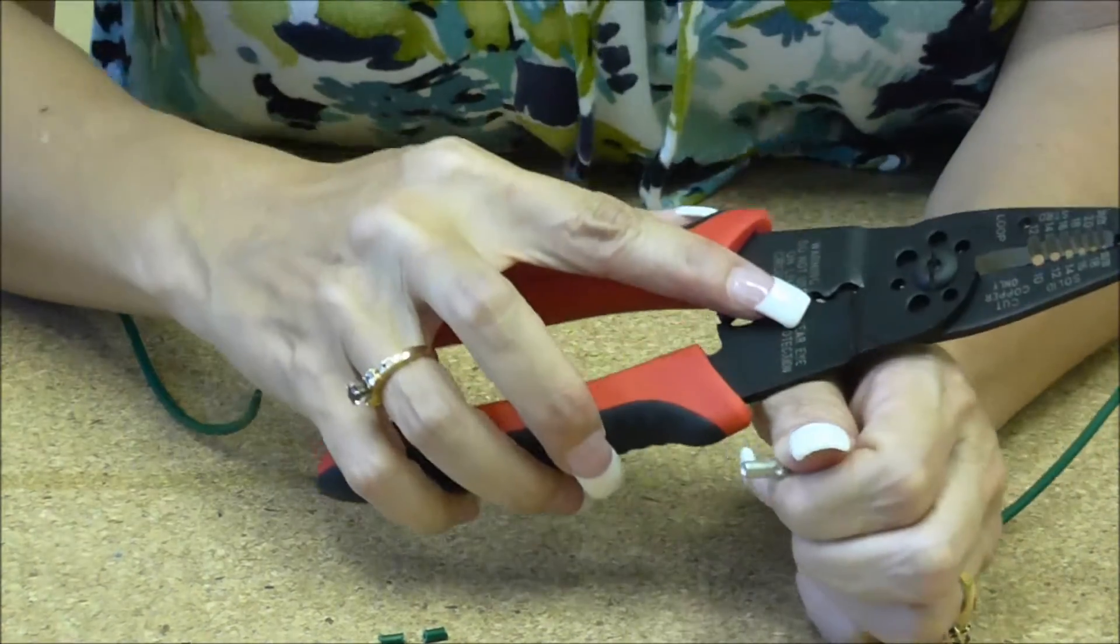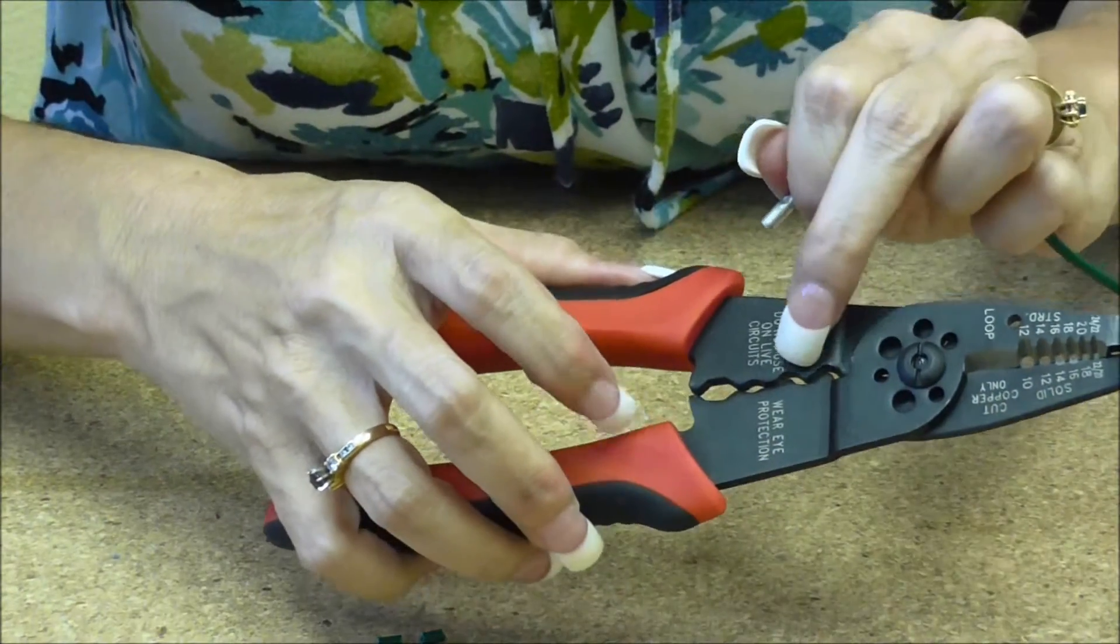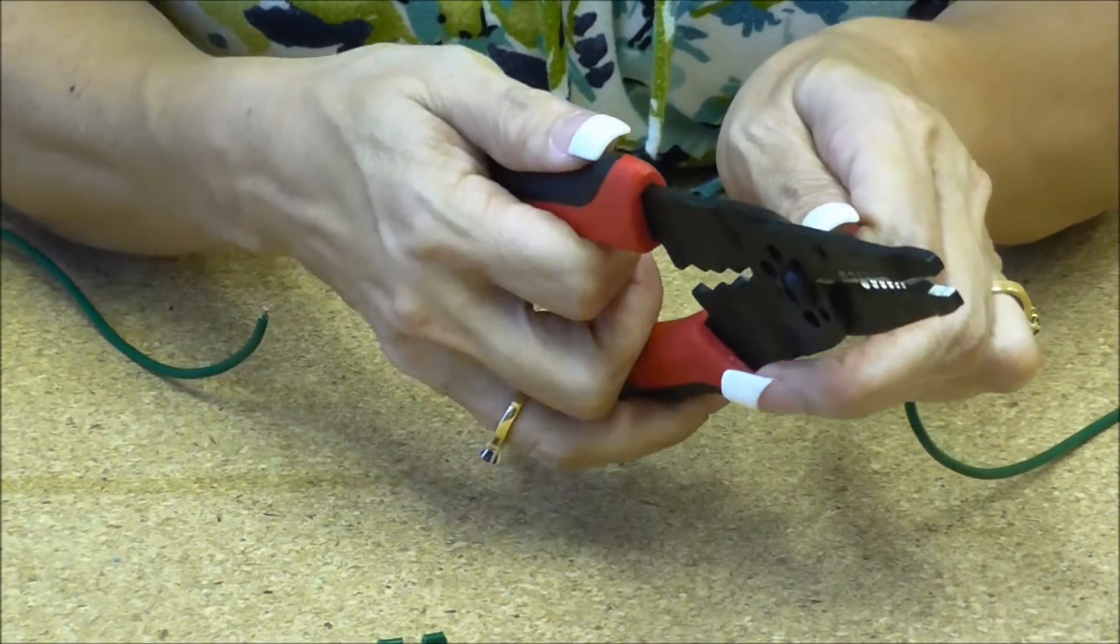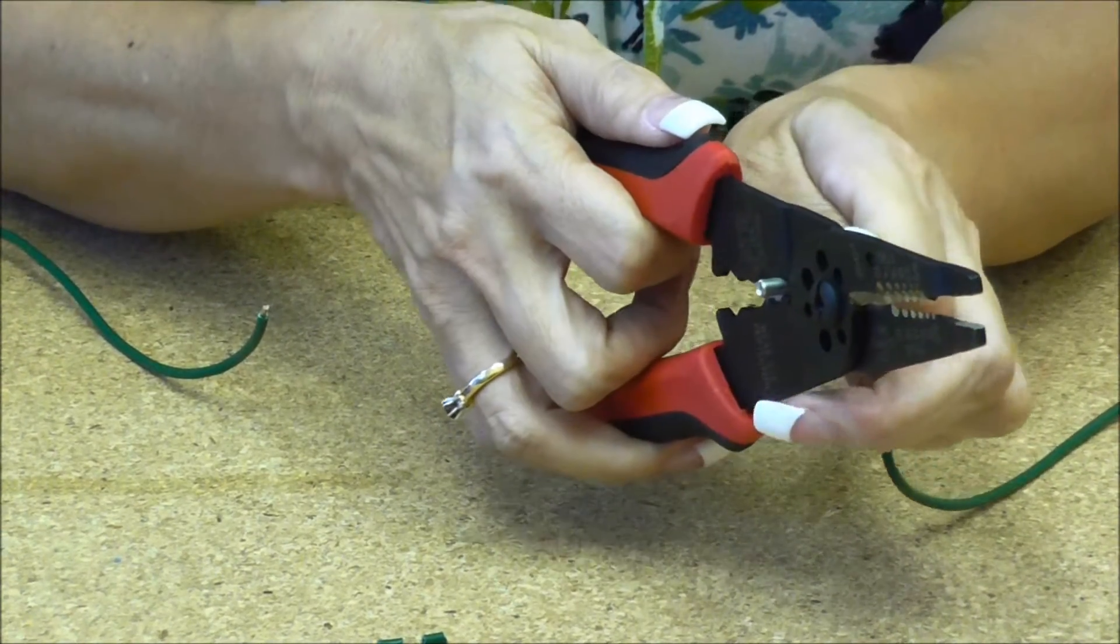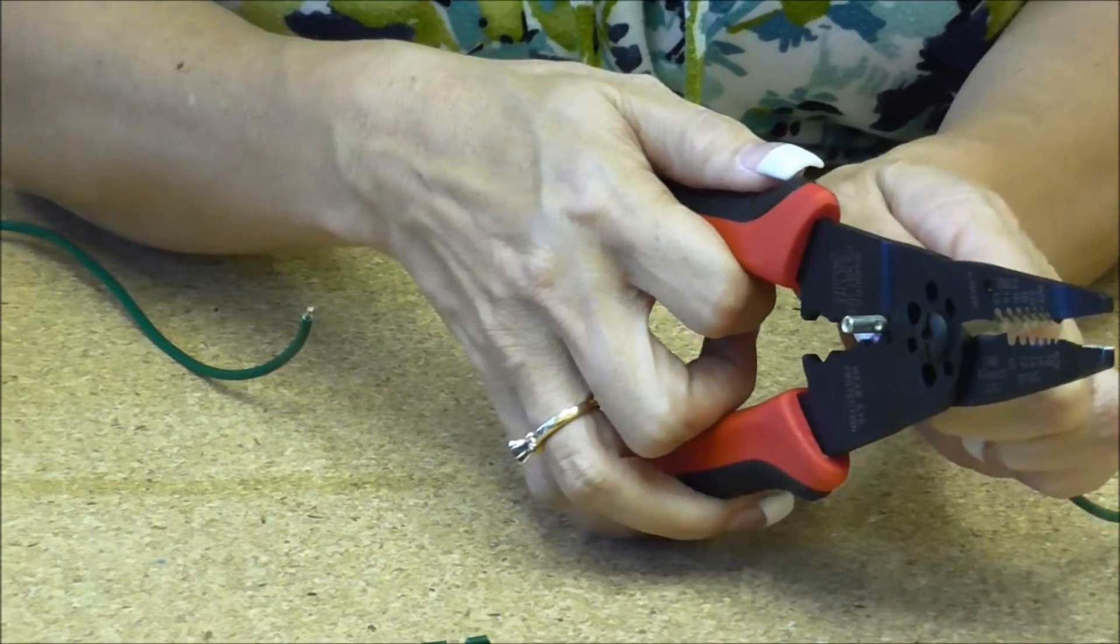When you're looking at your crimpers, you have to look where that bump is coming down. You do not want to crimp that bump down on that seam. You want the bump on your crimper to be on the other side.